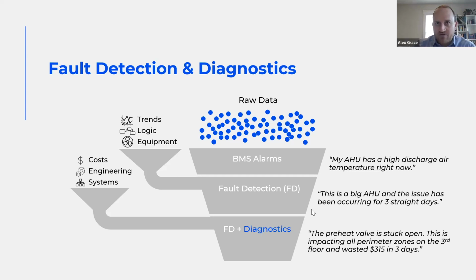When we start talking about fault detection and go a level deeper, we're now adding the concept of time. So it's not just an individual data point exceeding a threshold, I'm now looking at trends of data over time. I've got more logic involved. You might get something like: not only is it too hot, but this is a big unit, a big air handling unit, and that issue has been occurring for 3 straight days. So a little more context, more information that's important to decide whether it's an important issue or not.